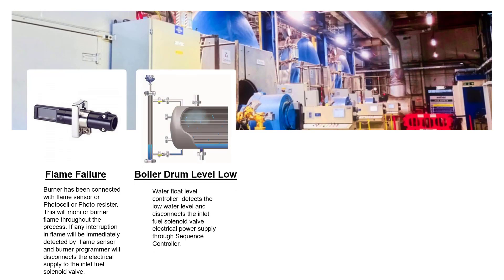Boiler drum level low: the water float level controller detects the low water level and disconnects the inlet fuel solenoid valve electrical power supply through the sequence controller.